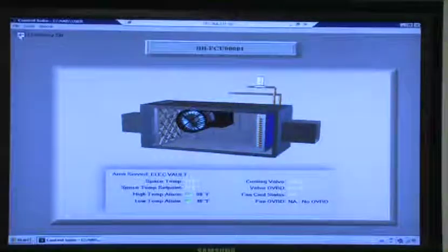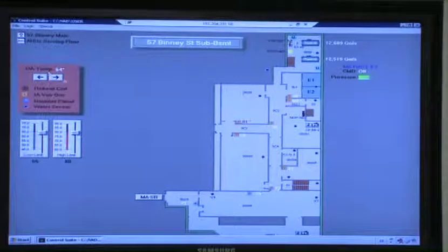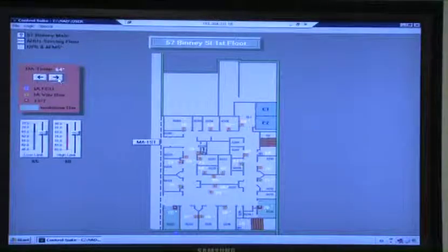Alrighty. Okay, so I'm gonna go up the building now. Now we're on the first floor. On the first floor, as we talked about before, now is there any flow measuring station in the basement? In the sub-basement, there's 2 exhaust fans. Any flow stations with them to tell us the flows? Only for the 2 exhaust fans. Alright, so we need that. James, we're missing that because I didn't see it. We're on the exhaust fan screen. You want the total exhausting from the floor? Yes.